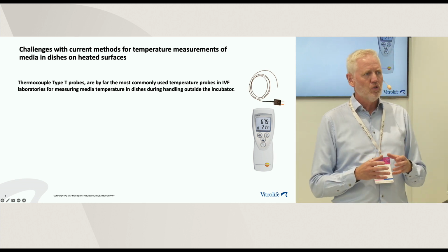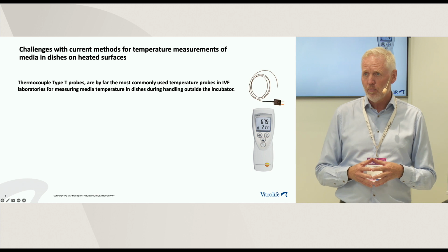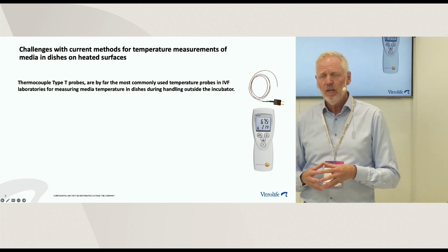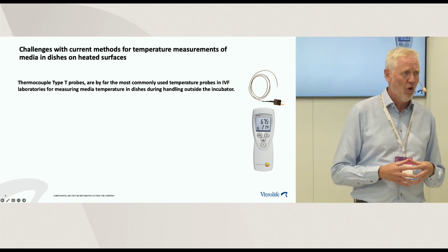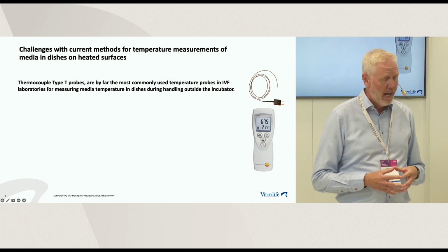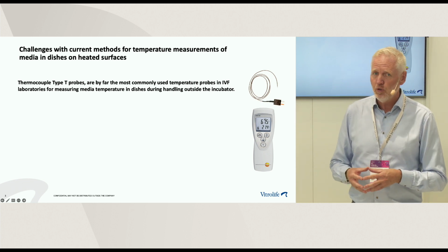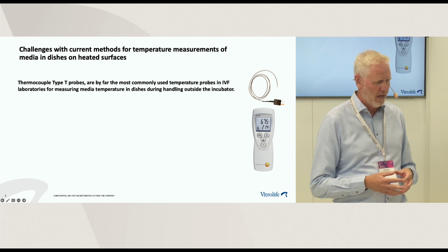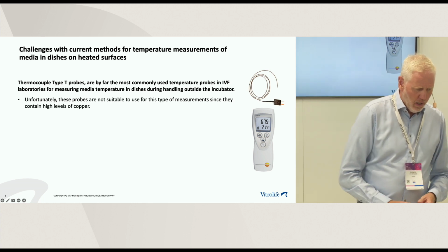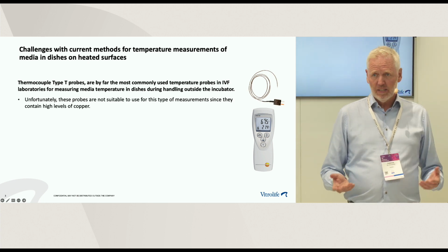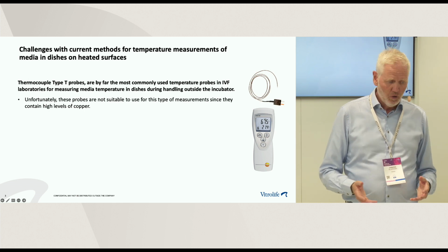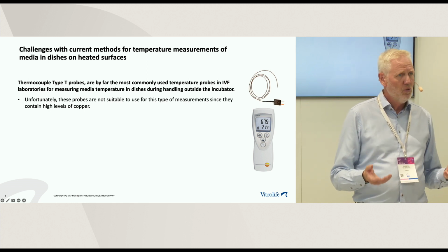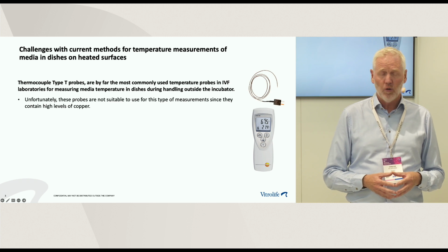And I will focus on one type of probe, a thermocouple type T, because that is by far the most commonly used probe in IVF. And that is also the worst to use, and you will soon understand why. So, this probe is, as I said, unfortunately not suitable to use. And it's not suitable to use because it contains a lot of copper.